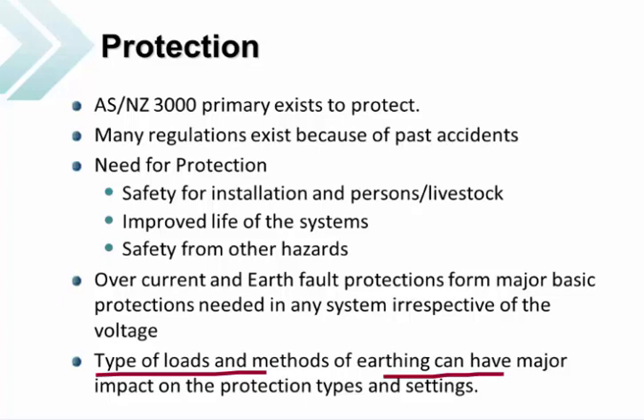There are two broad categories of functionality within an electrical system. The first is the ability to have the system deliver the power — that is the delivery of the energy. The other complementary part is, if there is a fault, because electricity is defined as a potentially hazardous medium, how the energy and in particular the current is actually diverted or used in a safe manner. That is generally one of the principles through grounding — the dispersion of the actual energy after a fault into a recognized point.